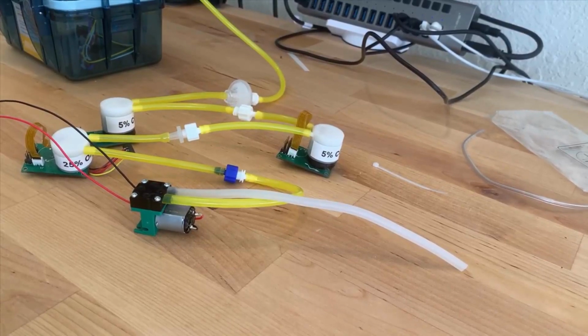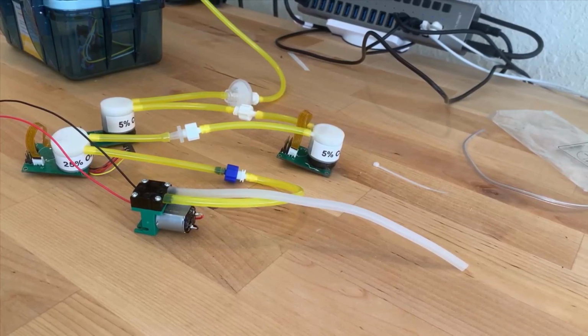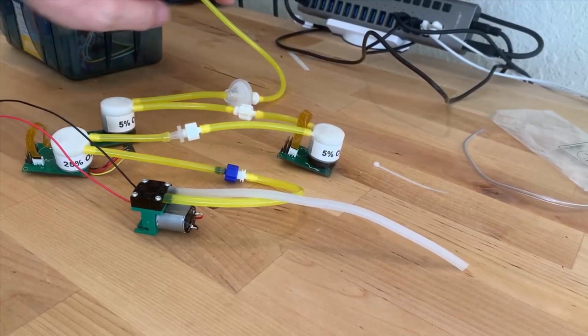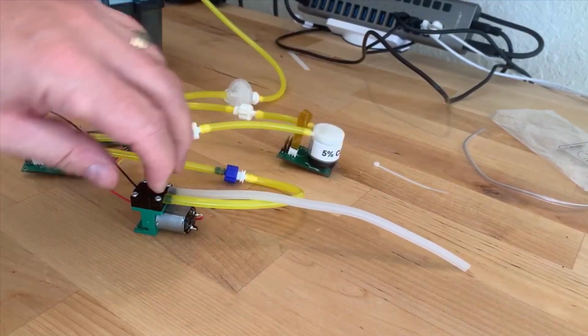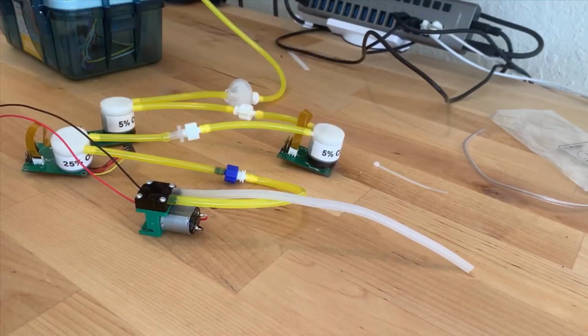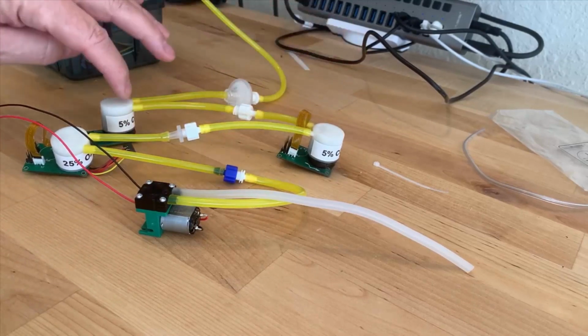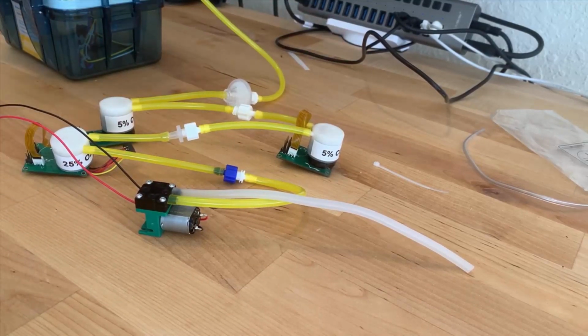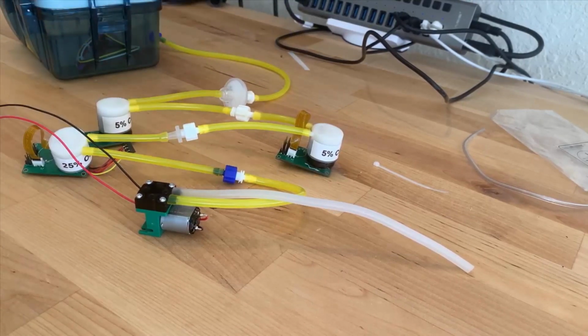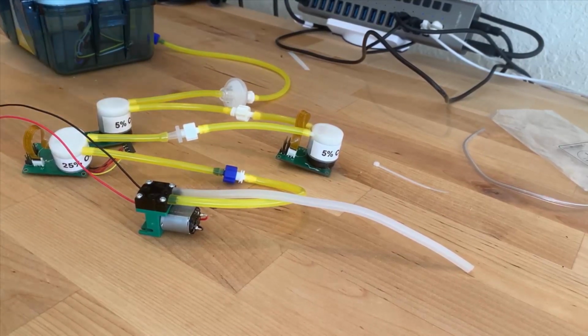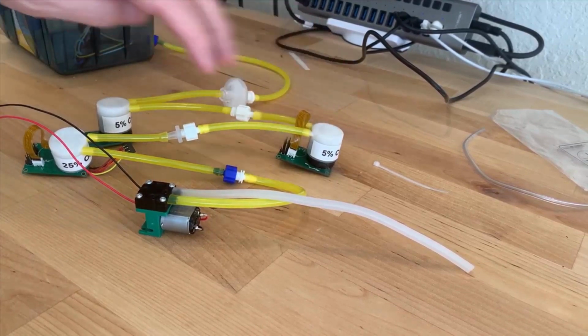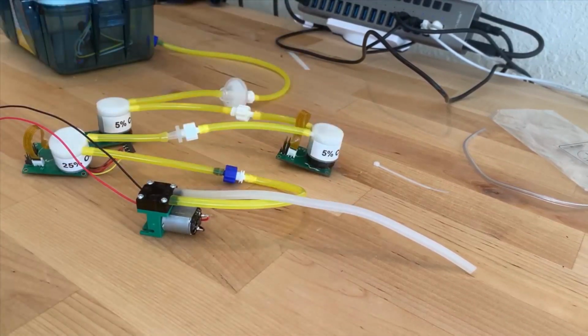Okay, what we're going to attempt today is just give you an illustration of hooking up multiple sensors via a pump for sampling. We've got a little box over here that we could be sampling from. But what we've done is we have a pump sucking on these three sensors. And so the input is coming in here, there's a little filter in there just to keep dust and any other crud out, you never know. And so it flows into this 5%, this 5%, this oxygen sensor through the pump, and out it goes.